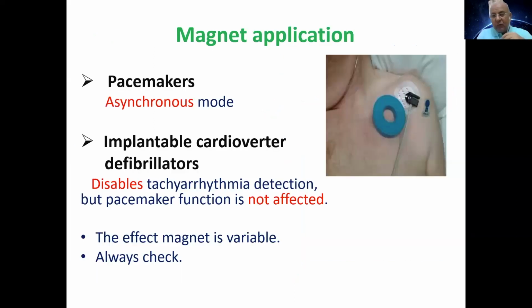So one important item, what is a magnet? Magnet application. The magnet is a very important item to understand our CIED. You put a magnet on the generator of the CIED. So you have to know where the scar is, and you have to feel this one, and where this is, and you put your magnet on. Usually there's a magnet sensor in the CIED. So this will sense the magnet, and it will block or affect the CIED.